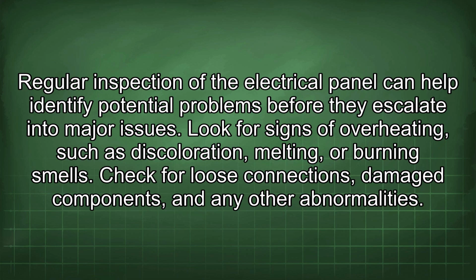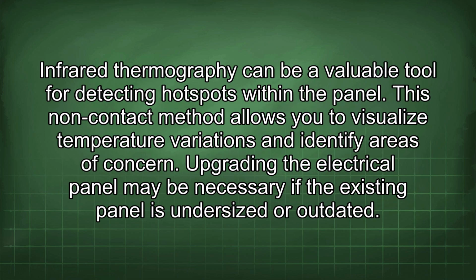Look for signs of overheating, such as discoloration, melting, or burning smells. Check for loose connections, damaged components, and any other abnormalities. Infrared thermography can be a valuable tool for detecting hotspots within the panel. This non-contact method allows you to visualize temperature variations and identify areas of concern.